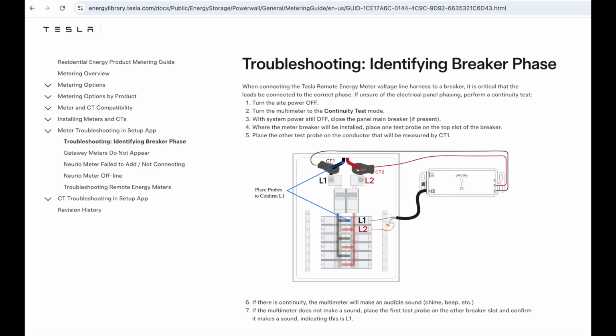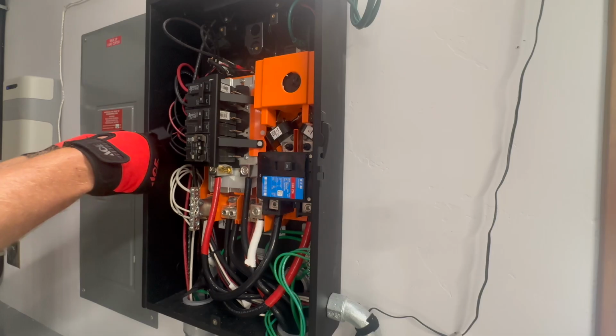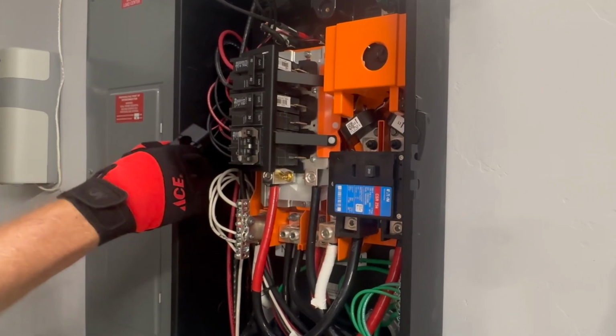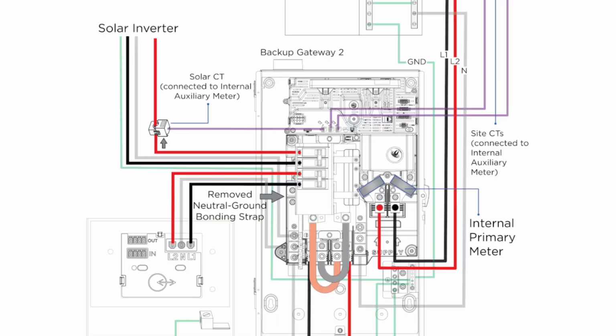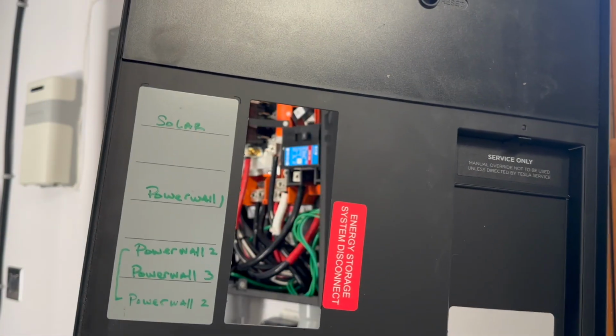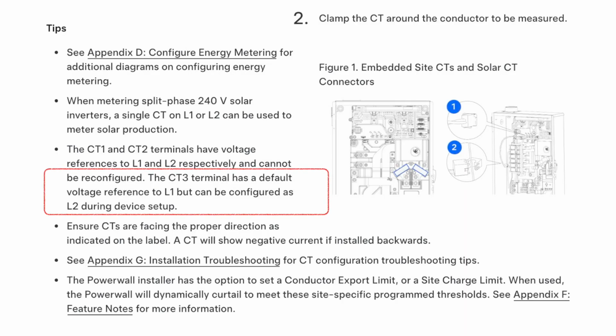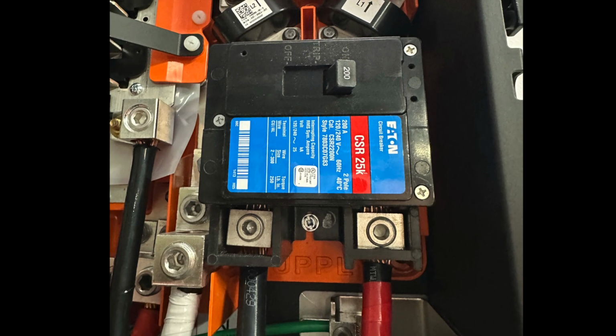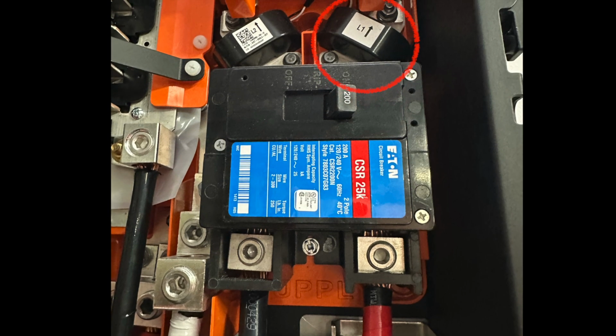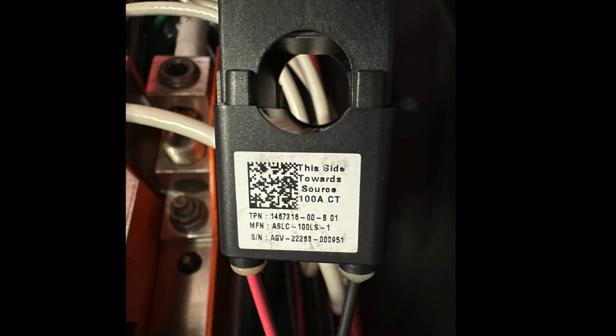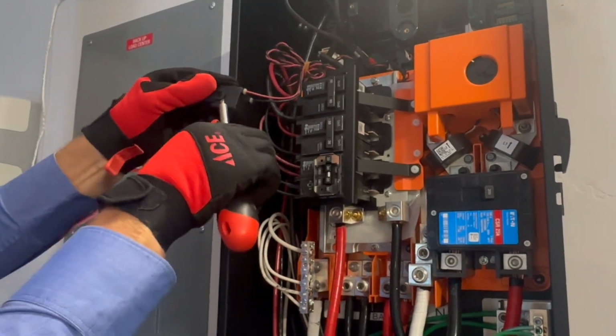Alright, back to uncovering why flipping those CTs wasn't quite right. Remember this unattached CT we found nestled in the backup gateway connected to the CT3 port? Well, looking through the install manual for the Backup Gateway 2, it's clear that this was intended to be the way that solar was measured. Okay, so what wire do we clip it around? Well, based on the labels on the breakers, we know that the top two wires are the combined solar input. The manual says that CT3 should be installed with respect to L1 by default. An inspection of the backup gateway makes it look like the red supply wire is installed as L1. The CT has a label on it and says that the label should be towards the source, in this case, the solar panels. So, that's all the information we need. And here I am installing the CT on the red solar wire.